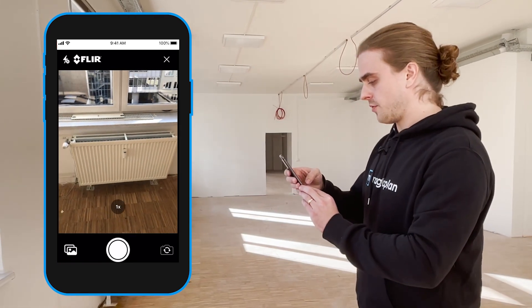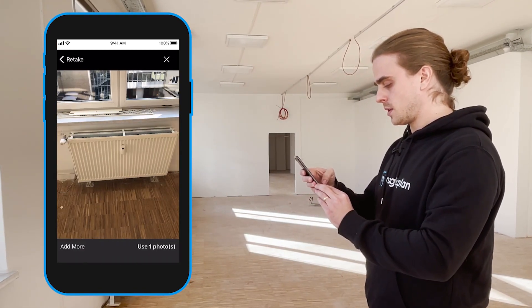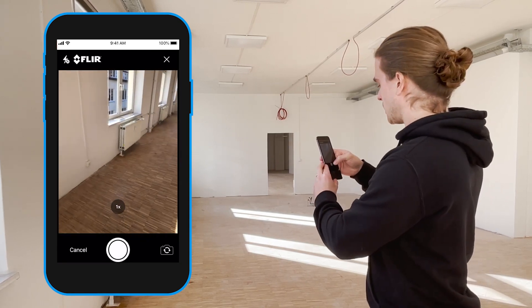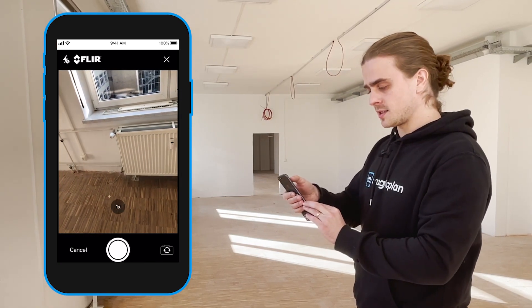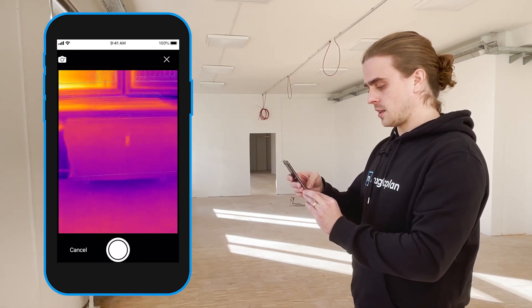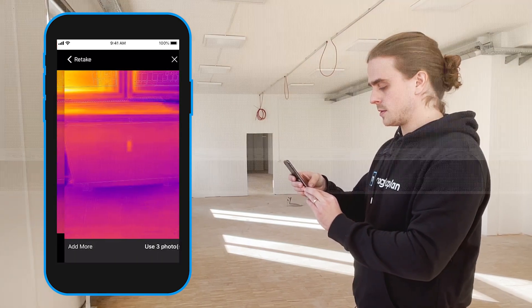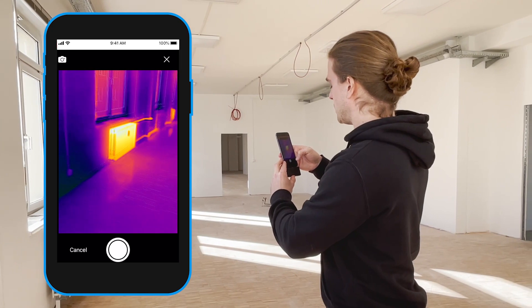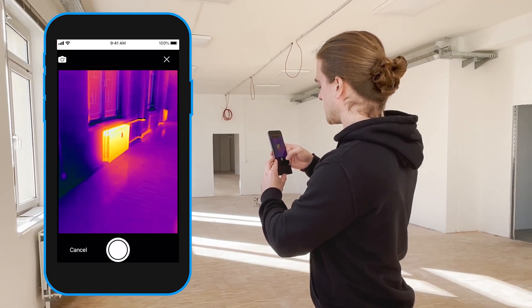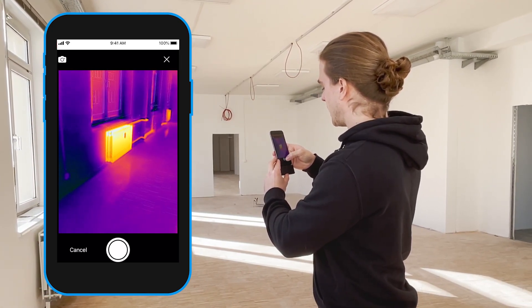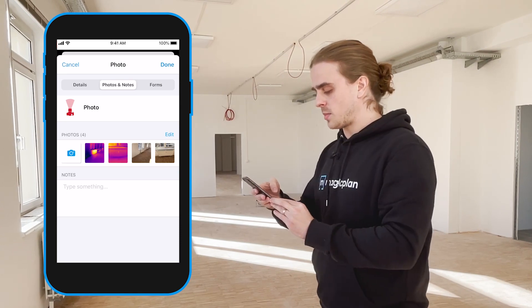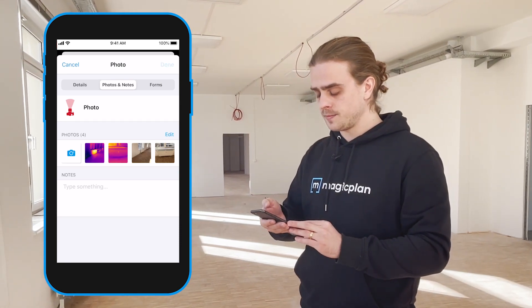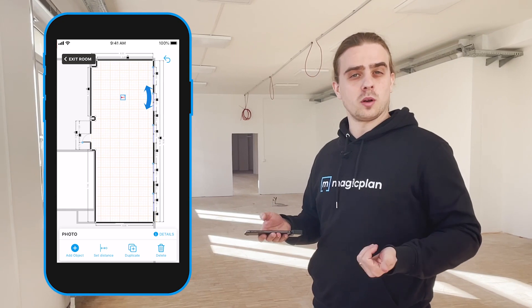Once you do that, I'll go ahead and take a photo of this heater that's not turned on. Let's go ahead and add a couple more photos — this one that is turned on. Now I'm going to select the FLIR icon in the top left, and as you can tell, this heater is definitely not turned on. But as soon as I rotate over to this one, you can see a very strong contrast between this heater and the surrounding area, which indicates that this heater is currently turned on. Once I've selected all my photos, I add them to that annotation and select done.